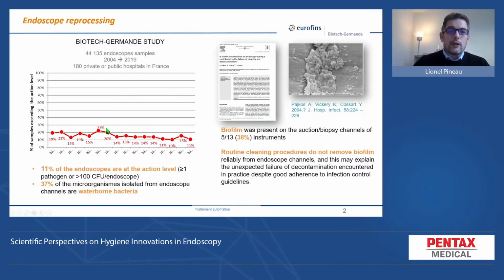2004, around 20% of the endoscopes were at what we call the action level, meaning that they contained at least one pathogenic bacterium or more than 100 CFU of non-pathogenic bacteria, and that they could not be used and should be quarantined. Even if we observe year after year that the results seem to be getting better, we still have in 2019 around 11% of endoscopes considered to be at the action level, which means they cannot be used. Of course, we can discuss a lot about what the target value regarding endoscope contamination level could be, but I will not spend any more time on that point.